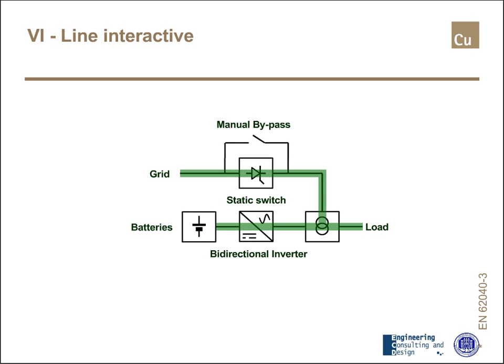The scheme of the VI UPS is shown in the slide. The load is fed directly from the grid through the static switch, and at the same time recharges batteries. But thanks to the bidirectional inverter, the voltage output can be adjusted by the UPS even in the presence of the grid.